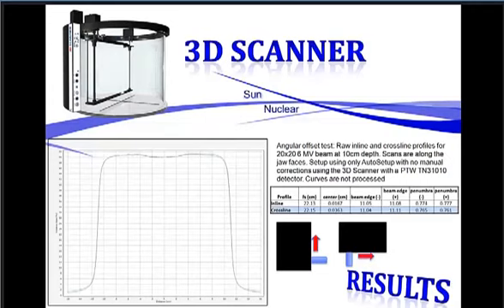We also do this with the MLC leaves. I don't have a slide of this. Retract the jaws, bring the leaves in, do the same type of scan and see if there's any skew in your leaf bank. Very sensitive to skew to the MLC leaves. You see very similar scans, but if you have some skew to your leaf bank, you definitely can detect it right away during your commissioning. Either have it adjusted or if it's within spec and you can't convince them to adjust it, then you can approach that however you feel you need to with that installer or service engineer.